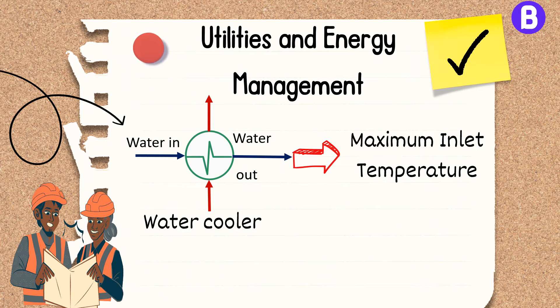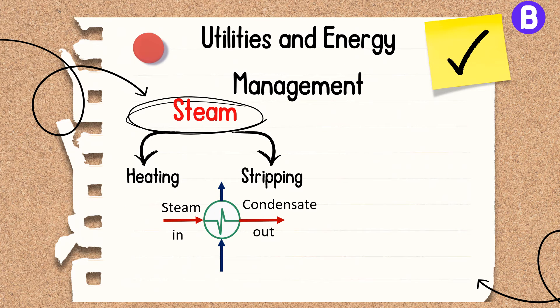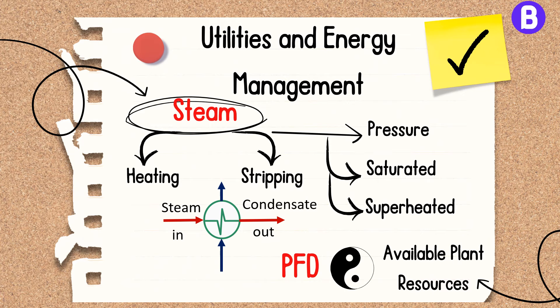For instance, when considering a water cooler in a PFD, it should account for the maximum inlet temperature of cooling water. If the plant has cooling water available at 25°C, we can't use it to cool a fluid below that temperature, and we should consider a reasonable temperature approach. Similarly, if using steam for heating or stripping, the PFD should consider the operating pressure of the available steam and whether it is saturated or superheated. A PFD should be in harmony with available plant resources; otherwise, we may need to add new utilities, increasing overall project cost.